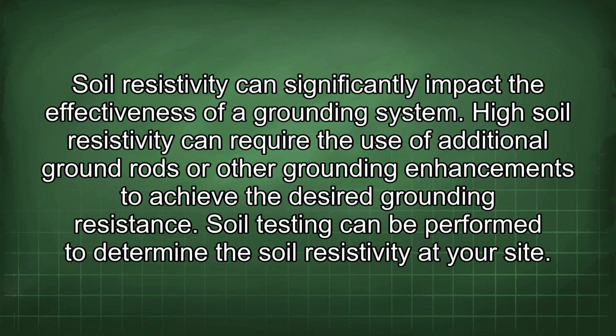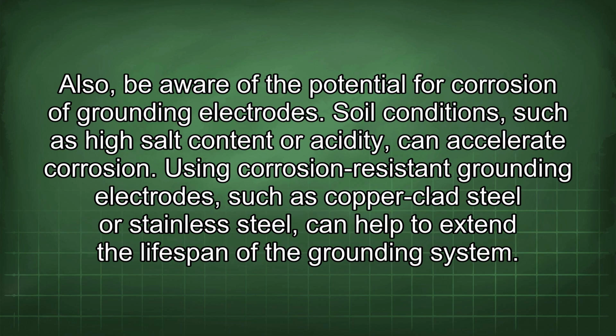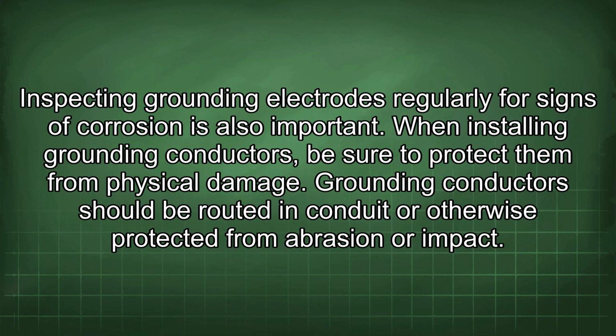High soil resistivity can require the use of additional ground rods or other grounding enhancements to achieve the desired grounding resistance. Soil testing can be performed to determine the soil resistivity at your site. Also, be aware of the potential for corrosion of grounding electrodes. Soil conditions such as high salt content or acidity can accelerate corrosion. Using corrosion-resistant grounding electrodes, such as copper-clad steel or stainless steel, can help to extend the lifespan of the grounding system. Inspecting grounding electrodes regularly for signs of corrosion is also important.